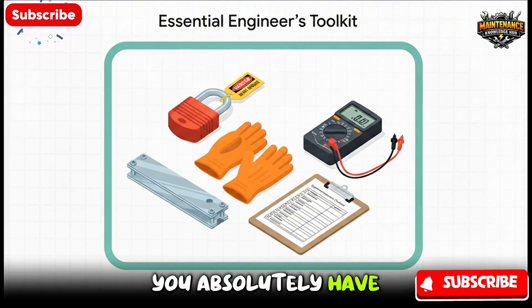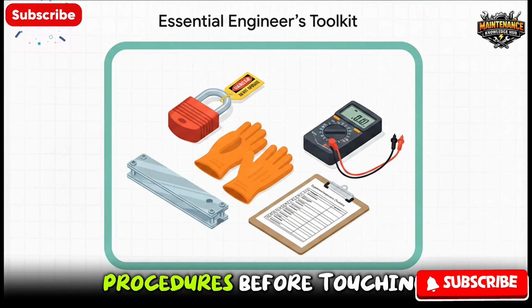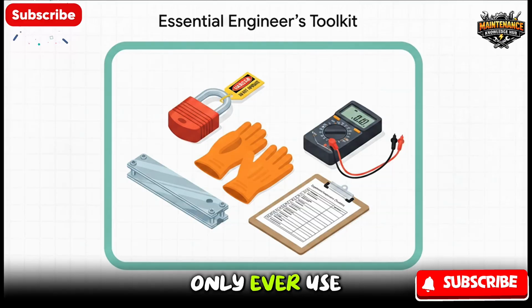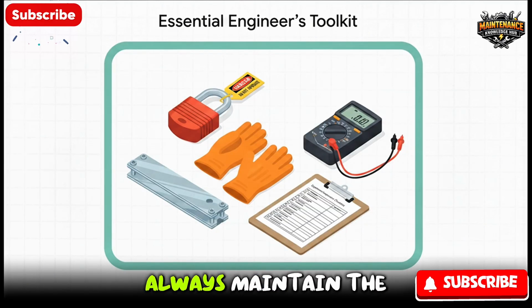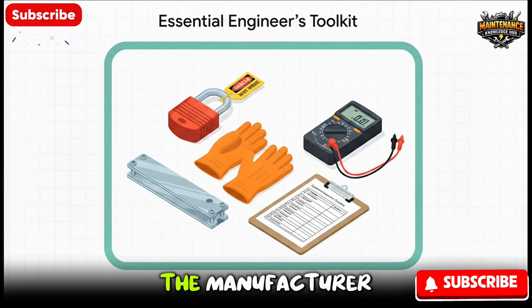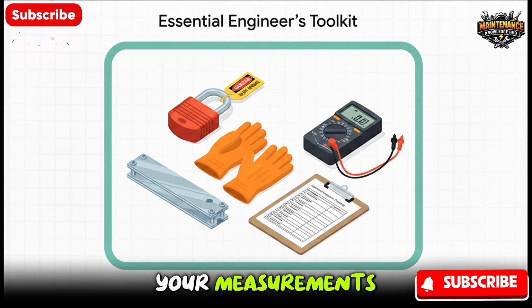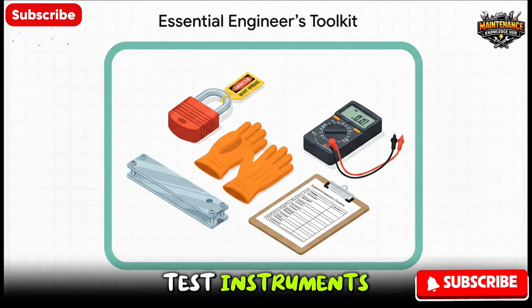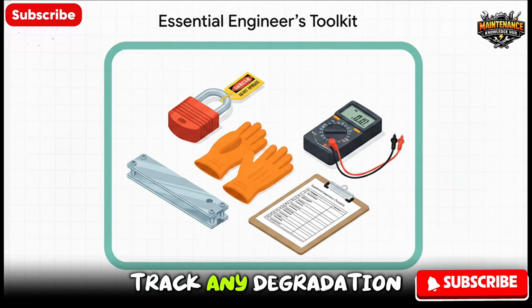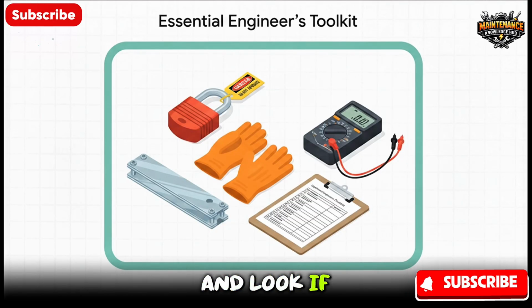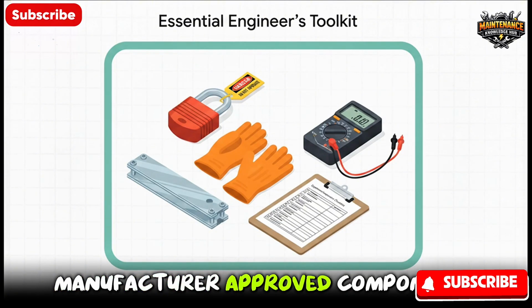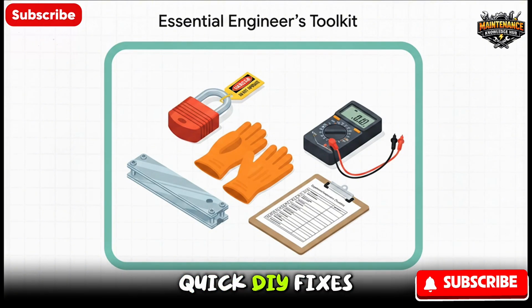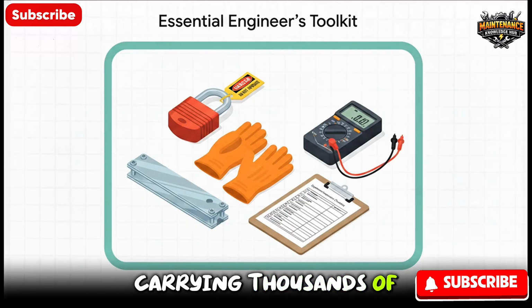You absolutely have to follow lockout/tagout procedures before touching a thing. Only ever use insulated tools. Always maintain the exact clearances specified by the manufacturer. Never just guess your measurements. Use freshly calibrated test instruments. Meticulously record all your inspection and test results so you can track any degradation over time. And look, if a section is damaged, you must replace it with compatible manufacturer-approved components. There are no quick DIY fixes on a system carrying thousands of amps.